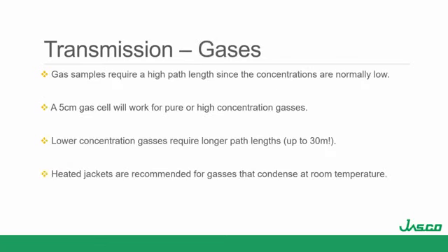All right, so transmission of gases. Gas samples require a high path length. The number of atoms in a gas is a lot lower than in liquids and solids, so a lot of times you need a high path length. You can go down to 5 centimeters if you're working with a pure or highly concentrated gas. For lower concentrations where you need longer path lengths, up to 30 meters is the longest I've seen.